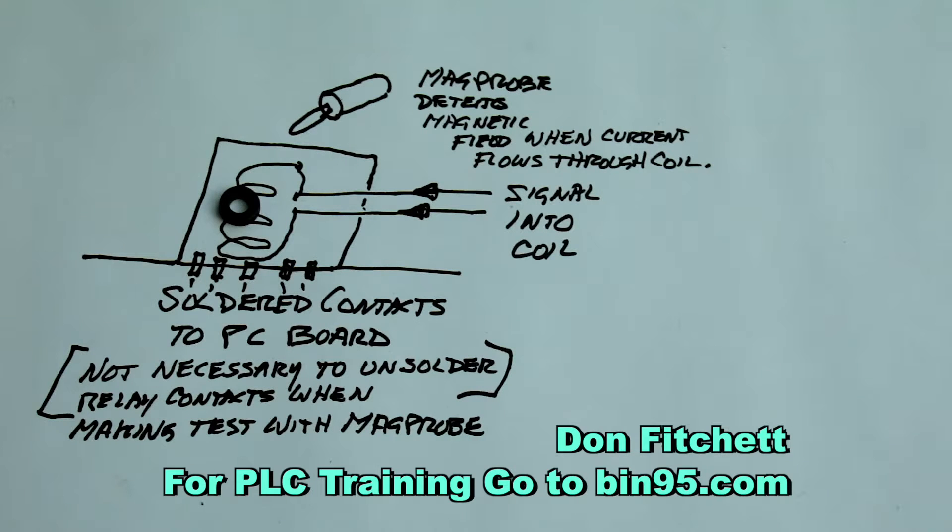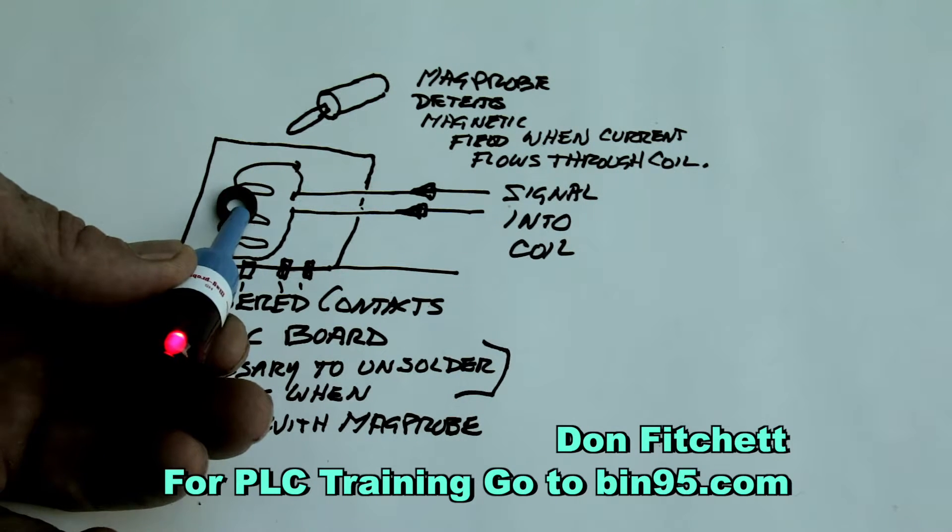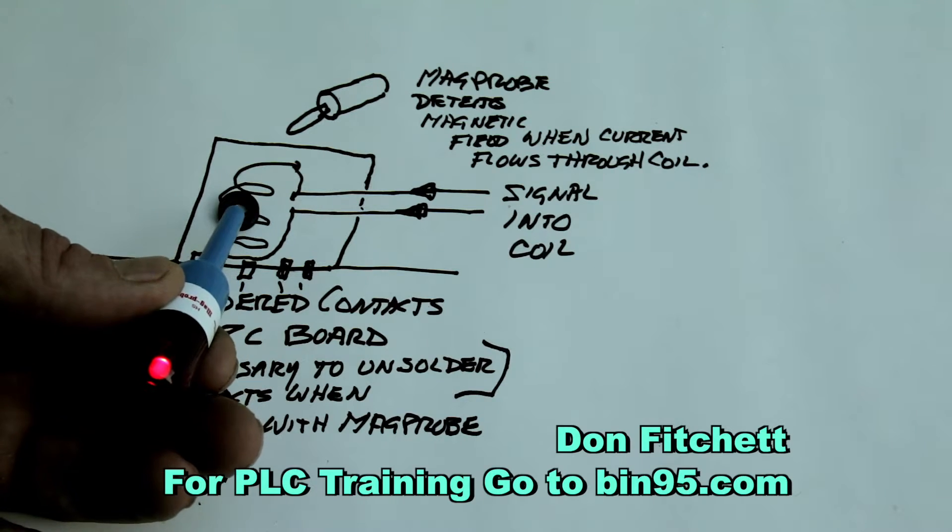Now if you're troubleshooting a PLC, this is really good too. PLC is sending the signal to some critical relays that are not doing their job and you want to find out if it's actually sending the signal. You just hold the mag probe up to the relay and instantly you know that you've got a signal from the PLC.